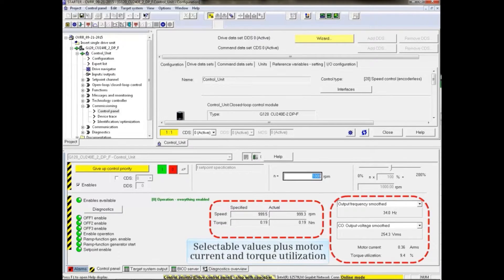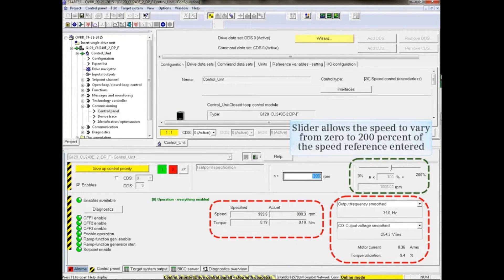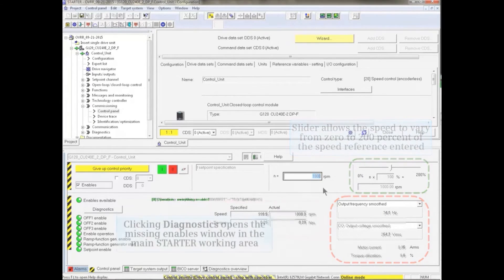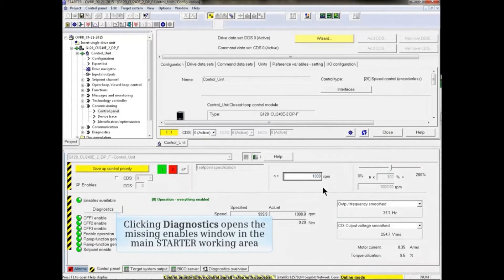There are also selectable values plus motor current and torque utilization shown. These areas are circled in red on the screen. Circled in green is a slider that allows you to vary the speed from 0 to 200% of the speed reference you entered. Clicking the Diagnostic button opens the Missing Enables window in the main starter working area.